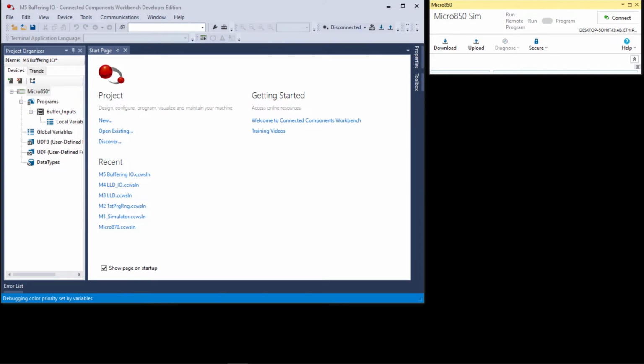Output bits are turned on or turned off as a result of your logic. Then when you're done scanning all the programs, it takes those memory location states and transfers them out hardware-wise to the actual output opto isolators, hence the screw terminals, operating devices. That is synchronous. It's the fixed scan cycle every single time.